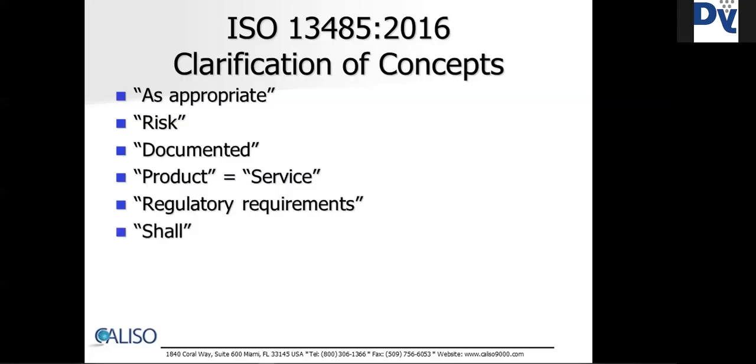ISO 13485 also uses the following verbs. Shall indicates a requirement. Should indicates a recommendation. May indicates a permission. And can indicates a possibility or a capability.